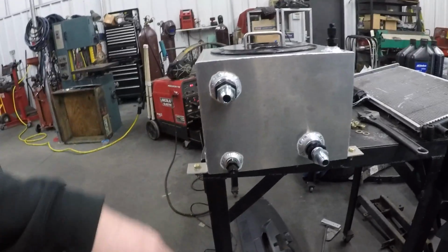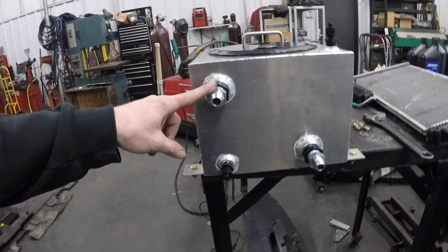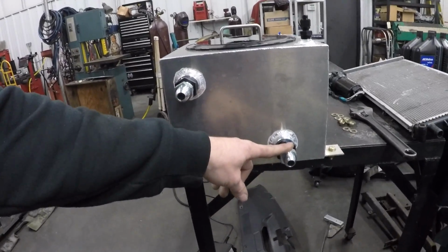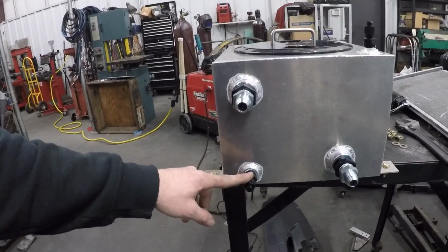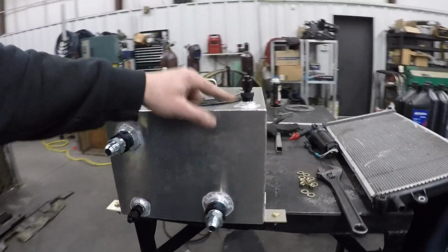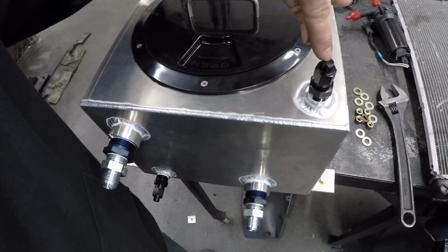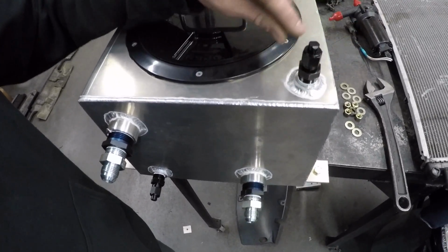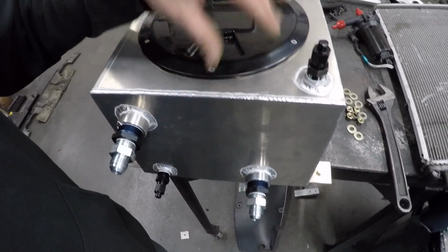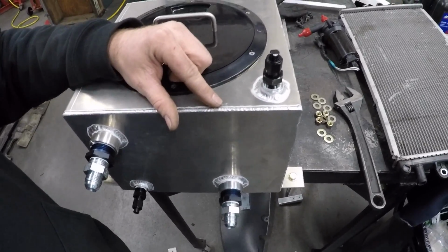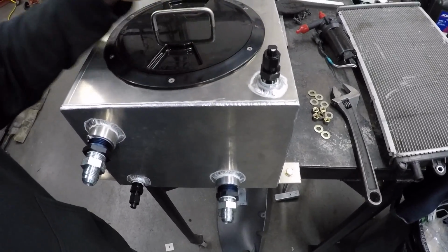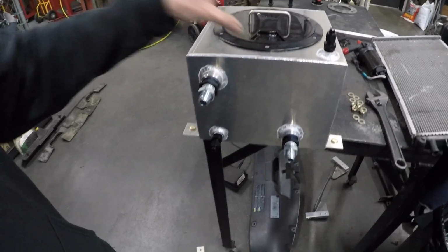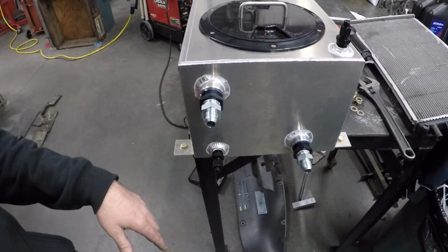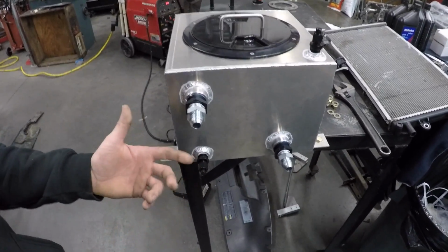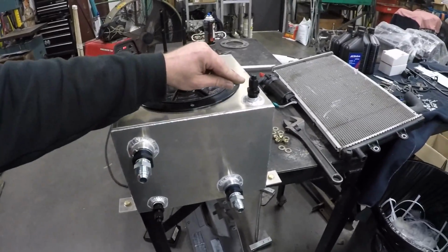So we have all of our fittings in the tank. This is going to be the return from the blower, this is going to feed the pump, this is our drain, and this is our vent. What I need to do is drill a really small hole in the top of this fitting and then tighten it down. This just allows for expansion and contraction of the fluid, so it's got somewhere to go. Because if you have this locked down tight and it builds pressure, you're going to end up blowing a line off or something like that. So as fluid gets hot, it expands. A small hole in the top of this will take care of that.